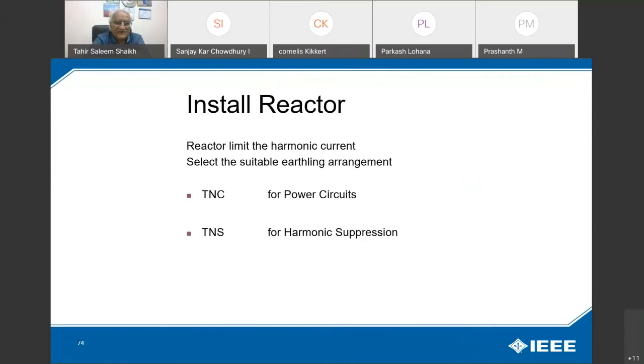TNC will represent a neutral and ground common in the distribution network, and TNS will have a neutral and ground separately from the source. At the source, the neutral and ground will be the same and connected. Apart from that, if you go further, TNS will have a separate earthing circuit, and TNC will have a combined one.